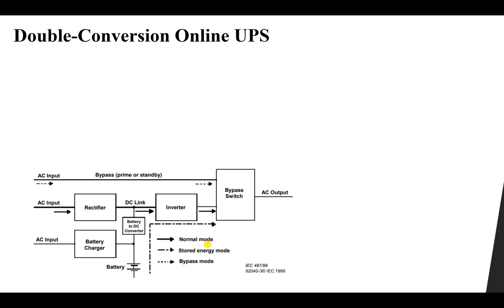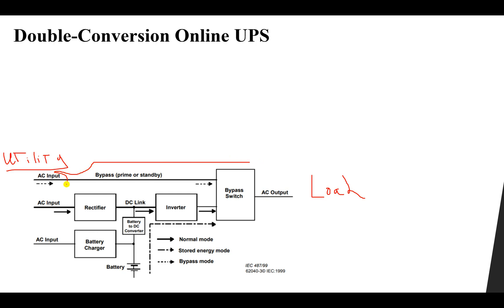The three modes are the normal mode, the stored energy mode, and the bypass mode. As you can see, we have the utility AC power here and our load. Between them we have the UPS system. The first mode is the bypass or standby mode, in which we take the input as-is and bypass it to the output. This is used in case of maintenance or any problem inside the UPS.